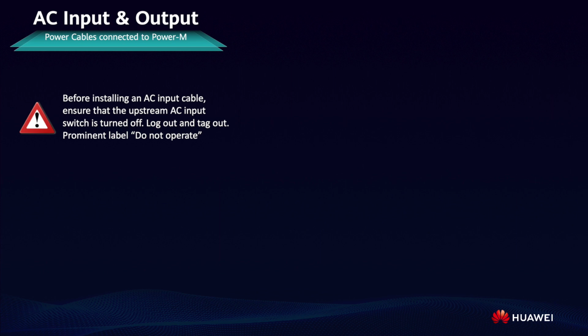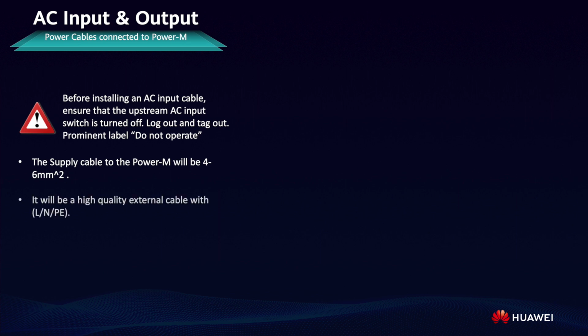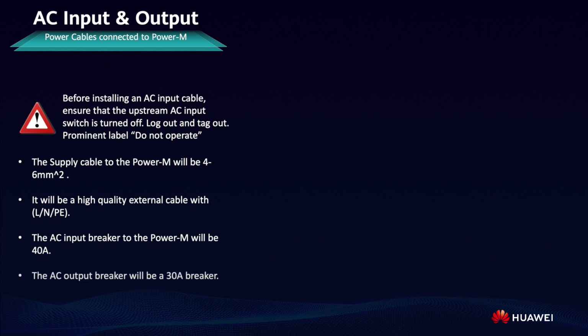Lock out and tag out with a prominent label. The supply cable to the Power M will be a 4 to 6 square millimeter cable. It will be a high quality external cable with live, neutral, power, earth. The AC input breaker to the Power M will be a 40 amp. The AC output breaker will be a 30 amp breaker.